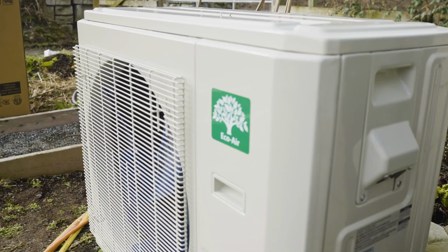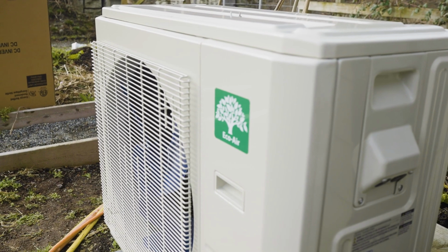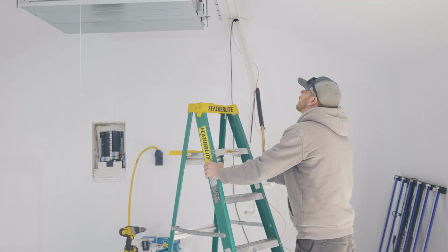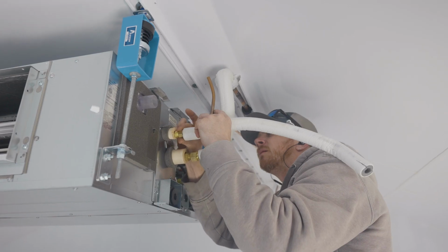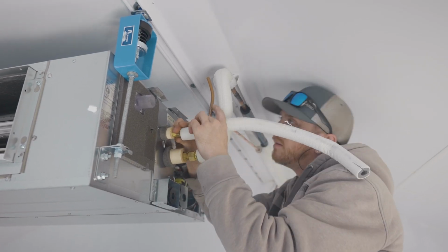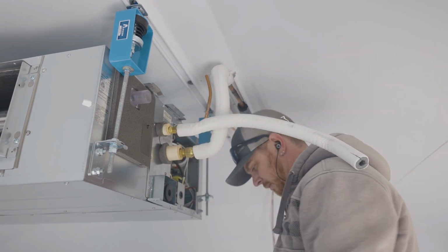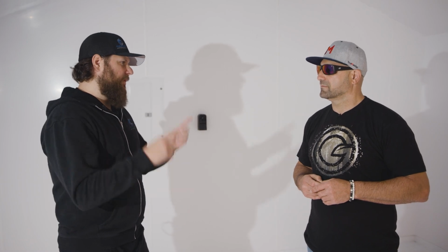So outside, heat pump compressor. This animal right above us is just the fan coil, the fan air coil handler. This type is a slim duct style that allows more higher static pressure, so you can go with slightly smaller ductwork, allowing more velocity out, which moves your air more in a turbulence type manner.